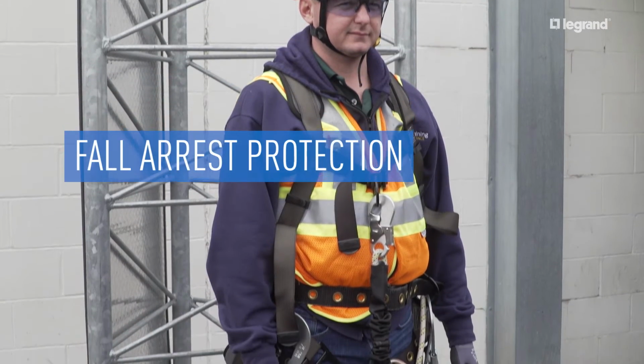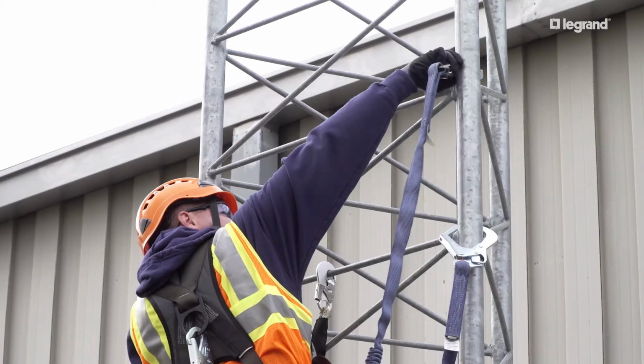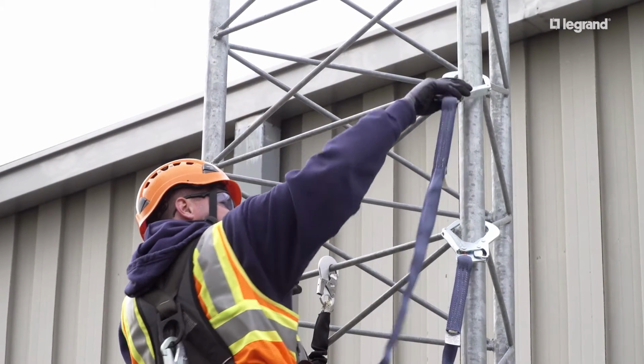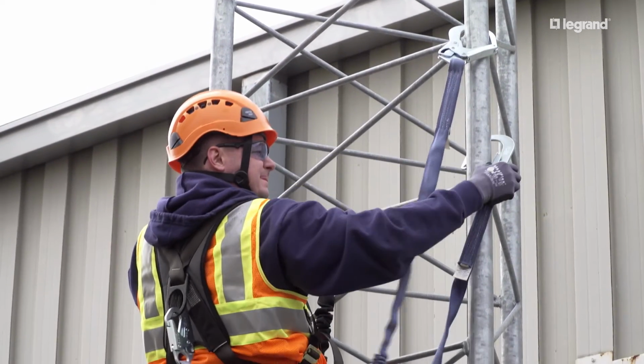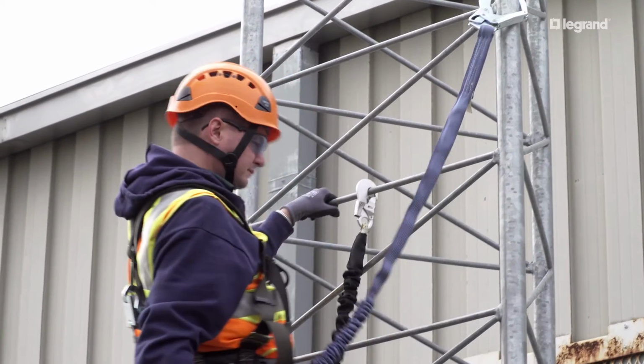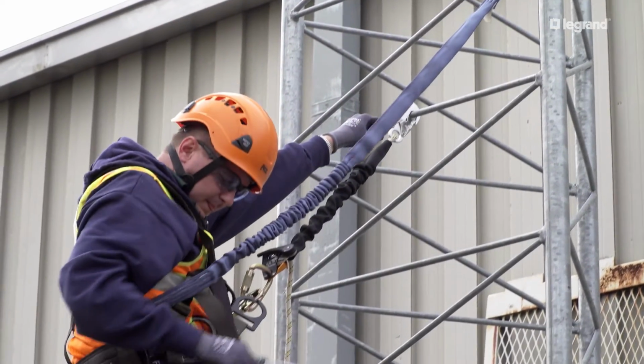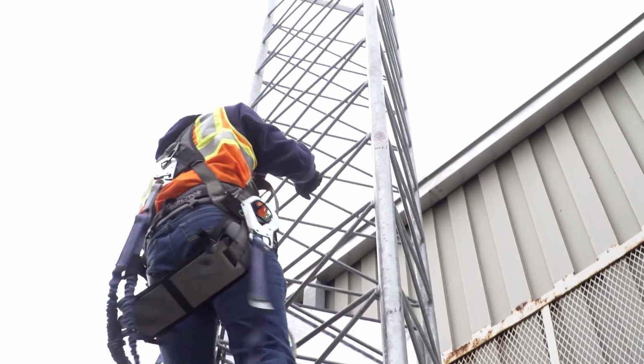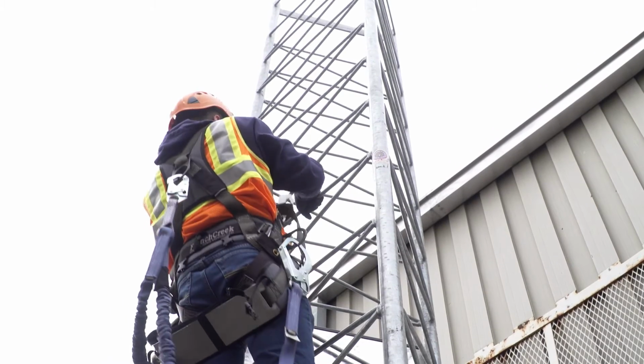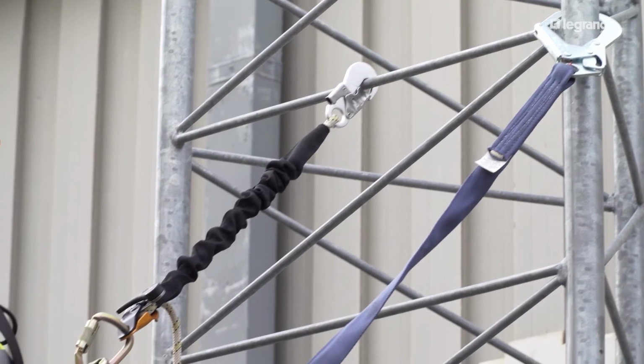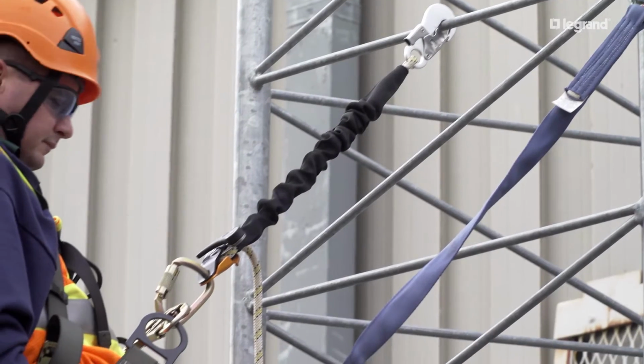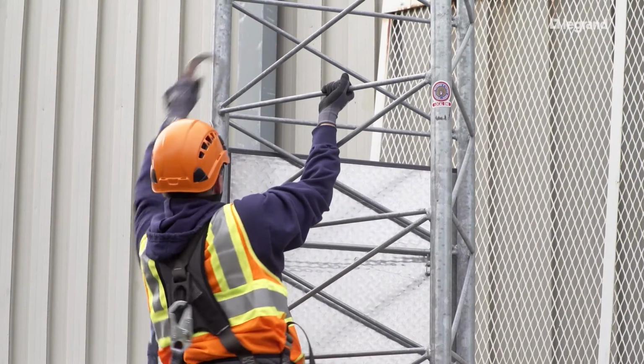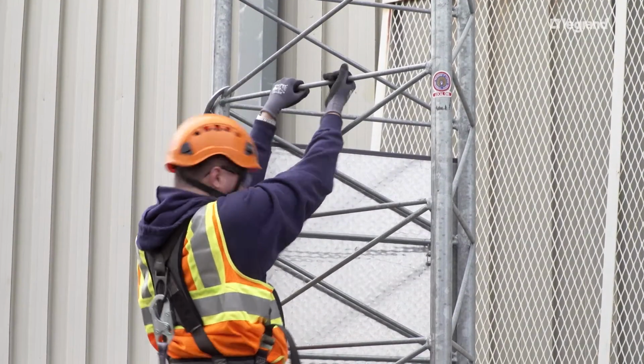Use appropriate fall arrest protection when required. Place anchors directly above or behind your work area to prevent a swinging fall. Use the shortest lanyard possible for the shortest potential fall. Always use planned or installed anchor points that are approved for safety. Always use lanyards with self-locking snap hooks. Never allow multiple workers to tie off to the same anchor point.